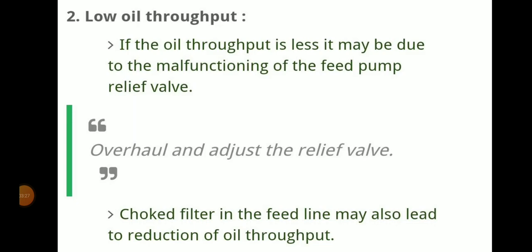Next is low oil throughput. If oil throughput is less, it may be due to malfunction of the feed pump relief valve. We have to overhaul and adjust the relief valve.